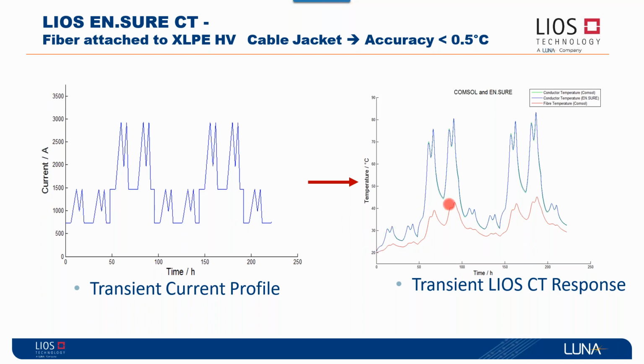And then you see in blue your conductor temperature. That means that if the fiber optic was away from the power cable and is at, as an example, 40 degrees Celsius, in reality your conductor is already at 80 and your limit is 90 degrees Celsius. So it's very, very important that we have the capability to have that. That helps operators understand how they can dynamically look at these lines and operate them. At the same time, we do a COMSOL analysis to prove our algorithm and to look at our accuracy.